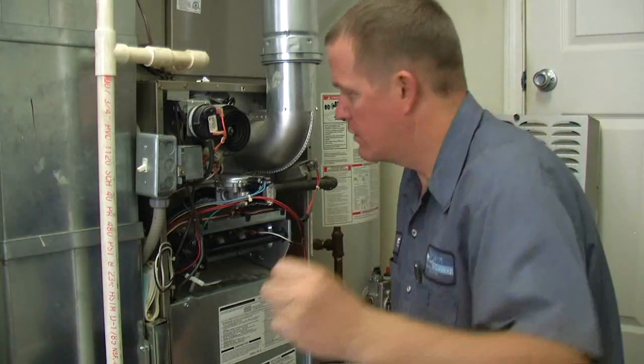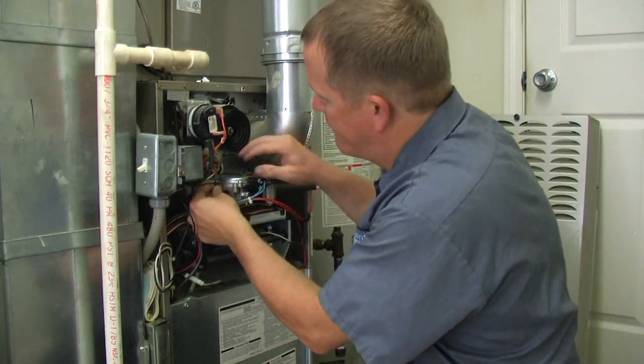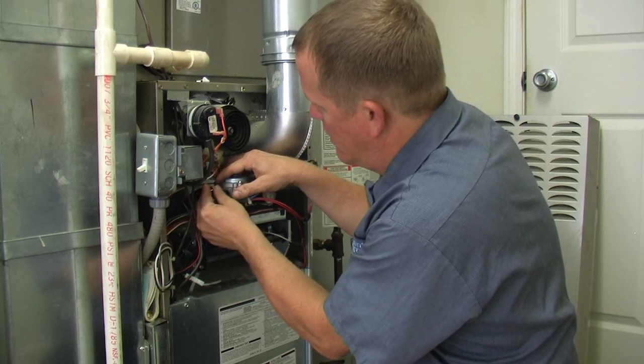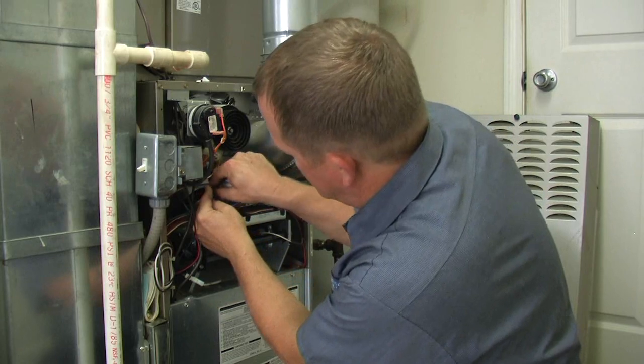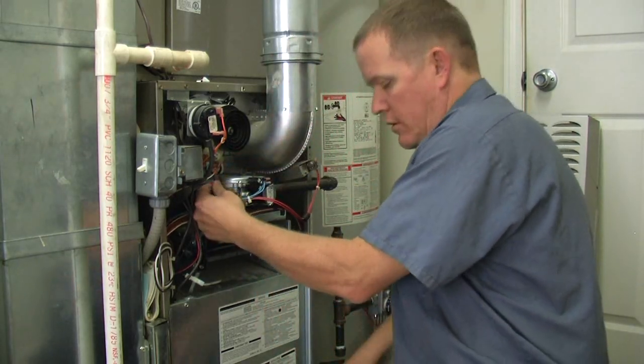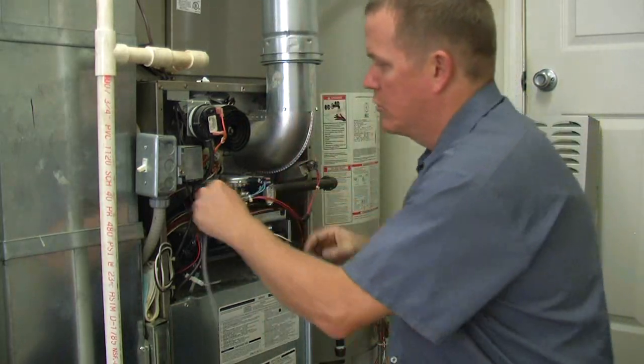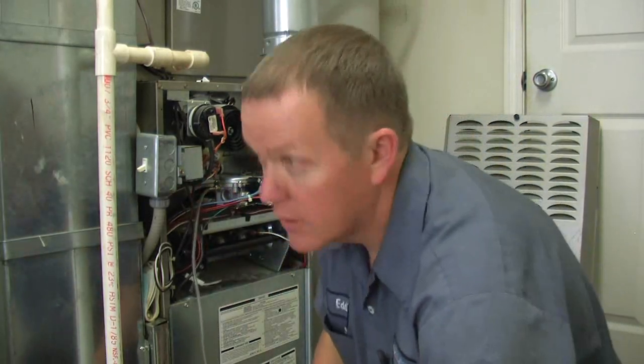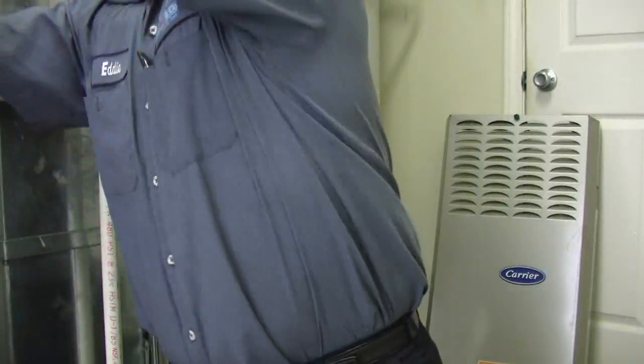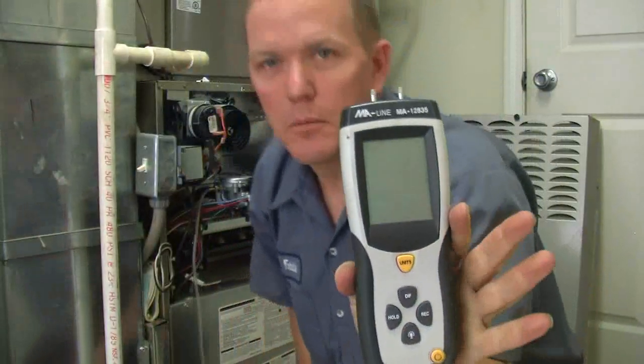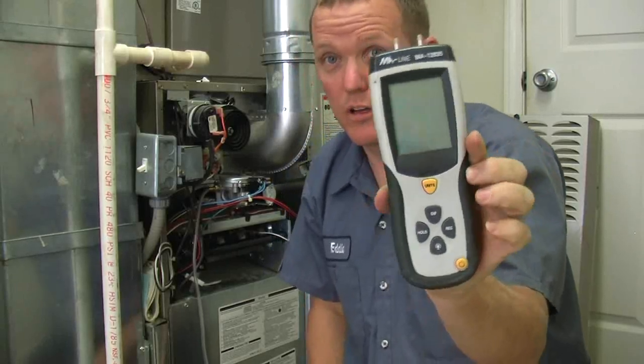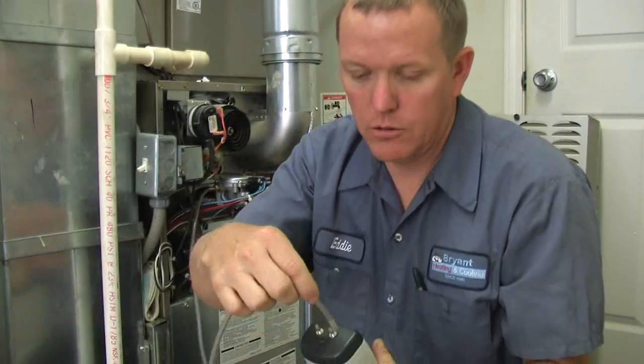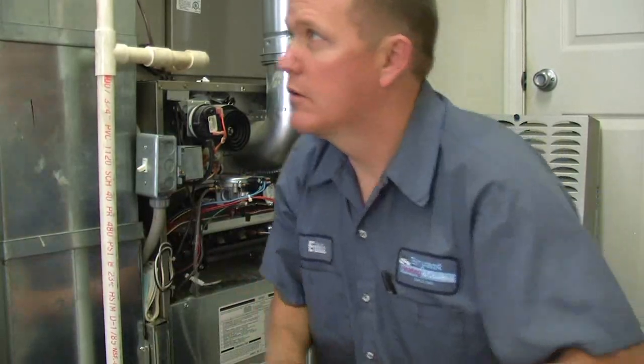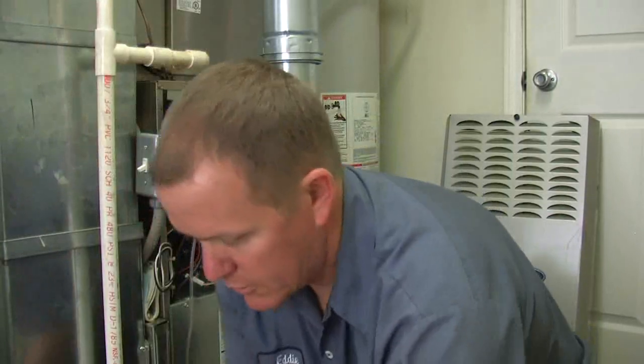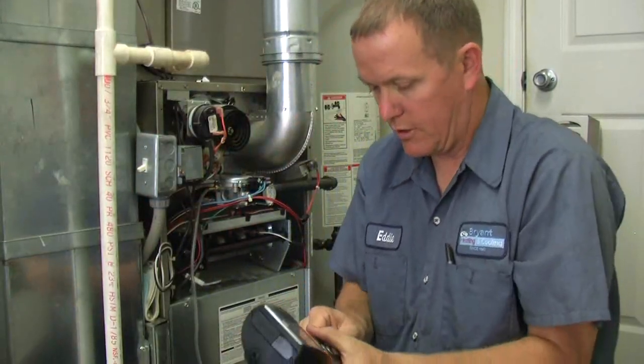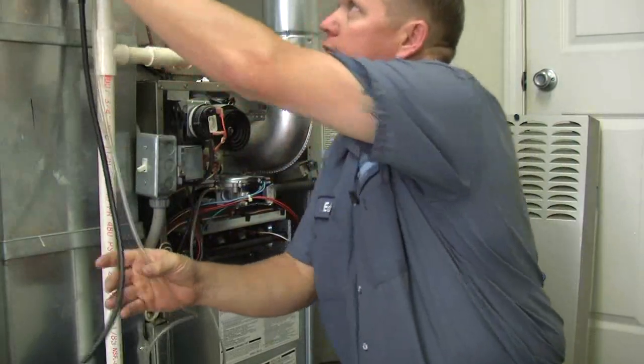Take your little barb, screw it in here. If I can get it started here. There we go. And I'm going to take my tubing, I'm going to hook it to that. You don't need a combustion analyzer. Let me show you. I've also got this manometer that you can use, or any manometer, to check gas pressure, but you would take your tube, connect it to the port, positive side. In my case, I'm going to connect it right to my combustion analyzer. So that part's done.